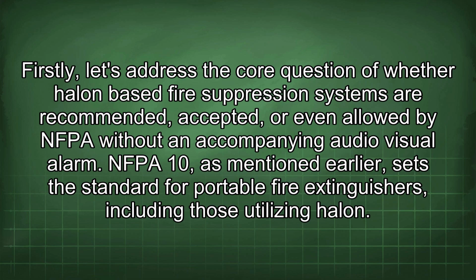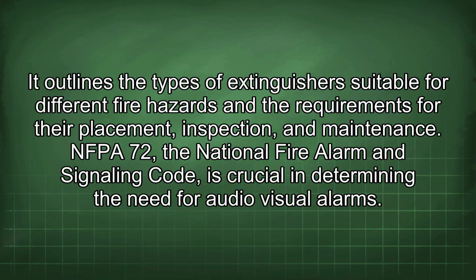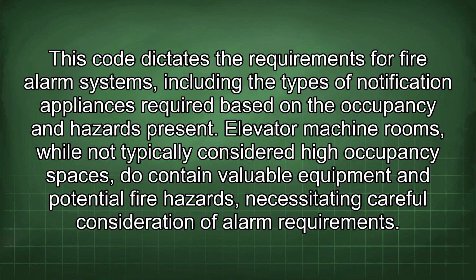NFPA 10, as mentioned earlier, sets the standard for portable fire extinguishers, including those utilizing Halon. It outlines the types of extinguishers suitable for different fire hazards and the requirements for their placement, inspection, and maintenance. NFPA 72, the National Fire Alarm and Signaling Code, is crucial in determining the need for audiovisual alarms. This code dictates the requirements for fire alarm systems, including the types of notification appliances required based on the occupancy and hazards present. Elevator machine rooms, while not typically considered high occupancy spaces, do contain valuable equipment and potential fire hazards, necessitating careful consideration of alarm requirements.